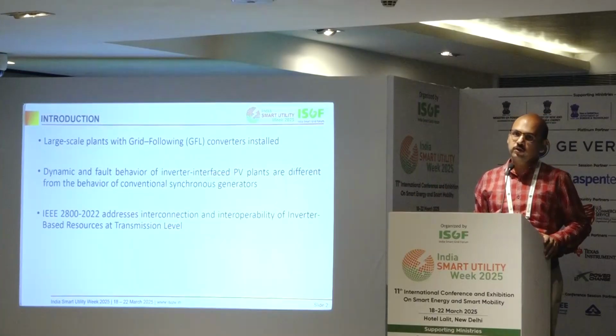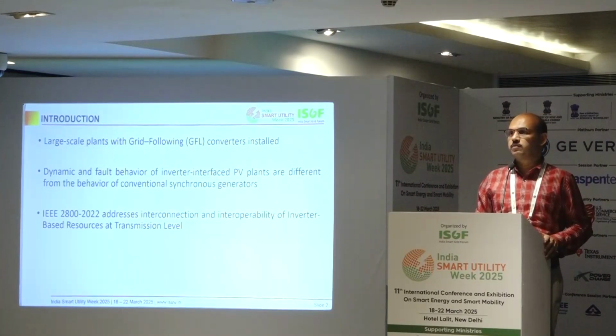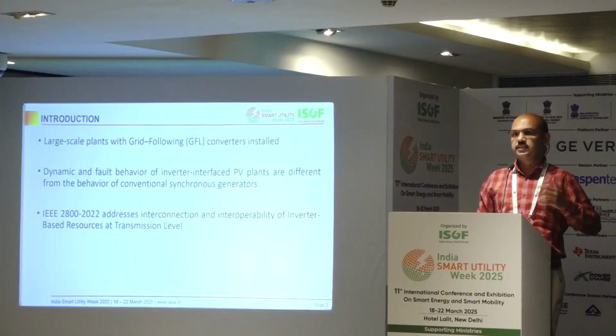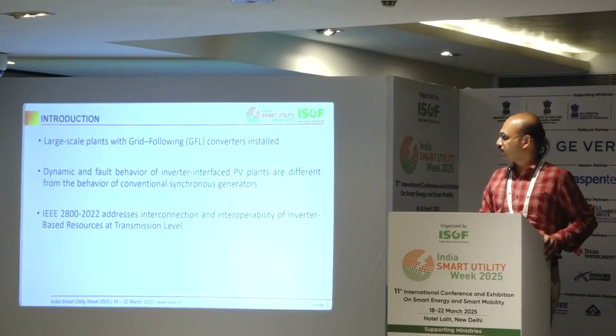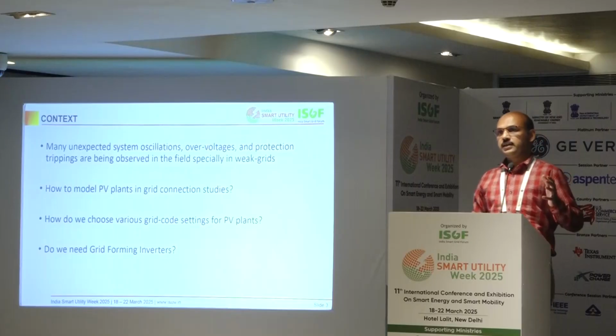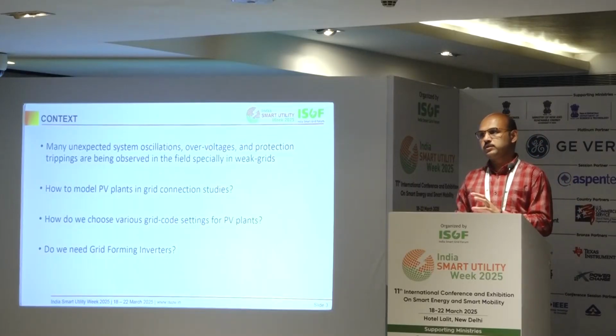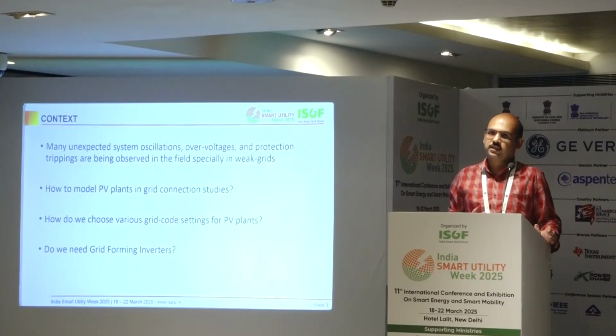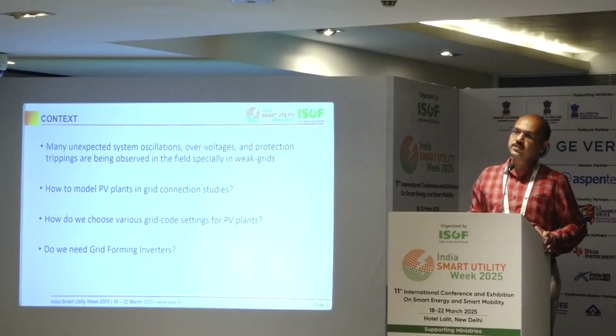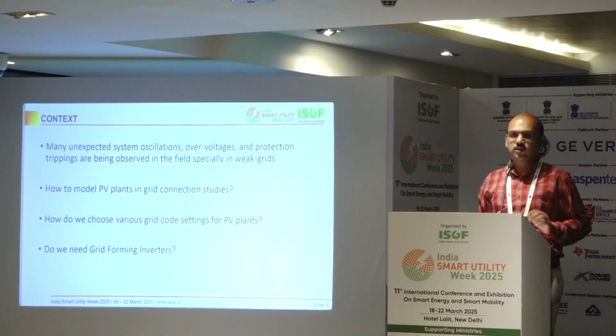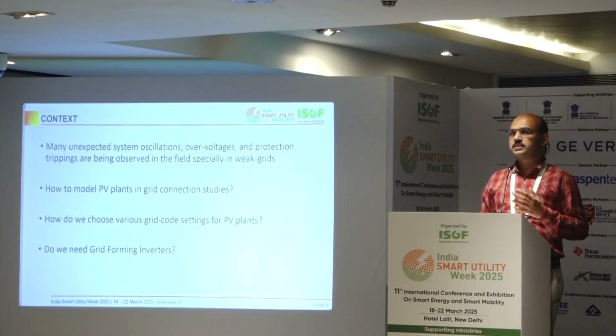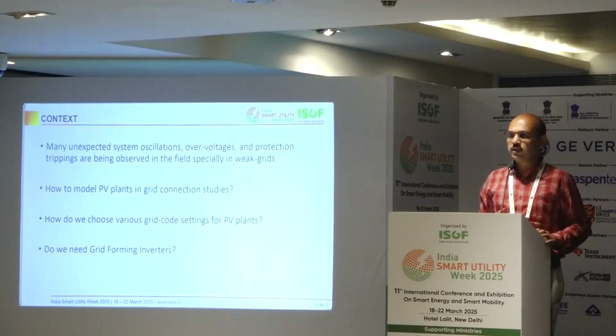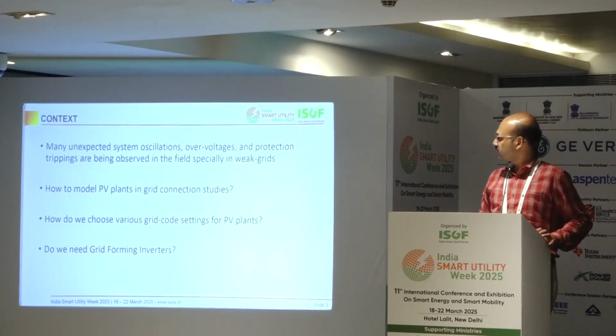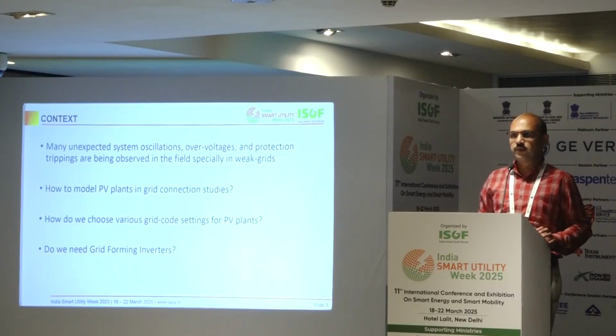So what we know is not applicable now for this kind of system. IEEE 2800 has come up to address some of the interconnection issues and gives a lot of guidelines regarding that. Till now we don't understand inverters well, and if we try to apply our knowledge of synchronous generators to inverters, it will not work. As a result, even though we are installing large scale plants, we have a lot of overvoltages, oscillations.